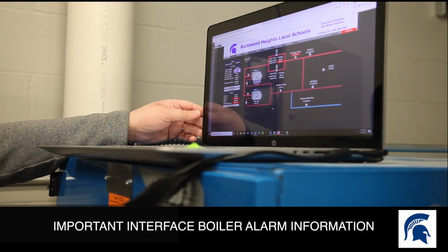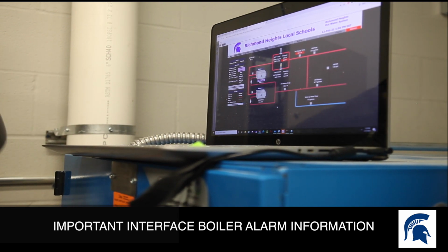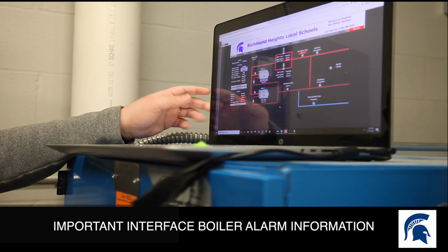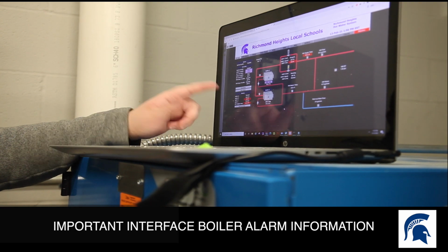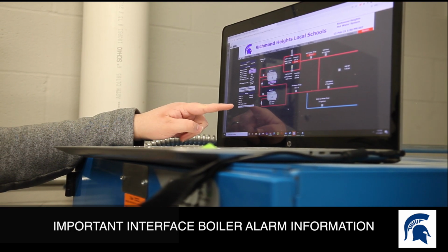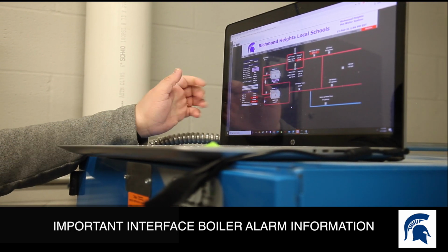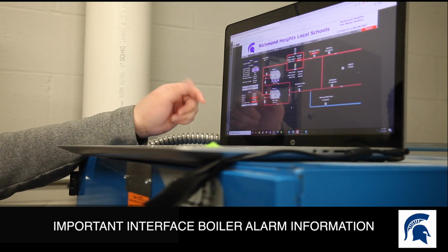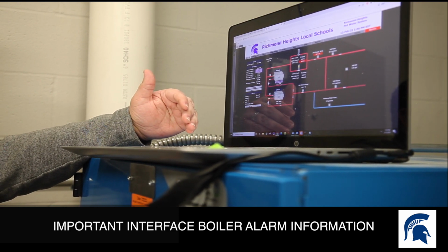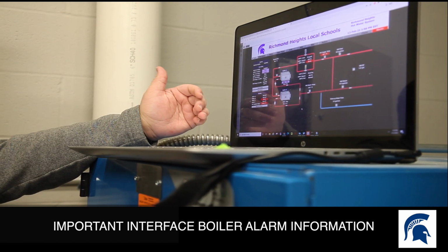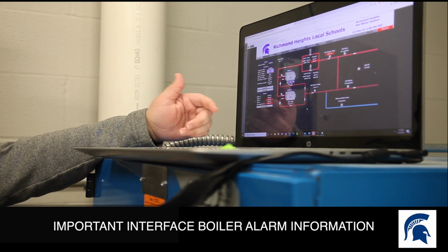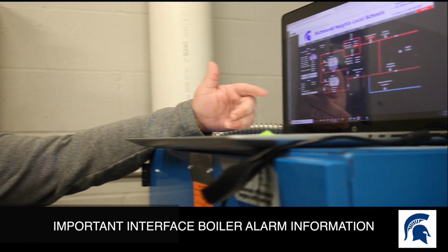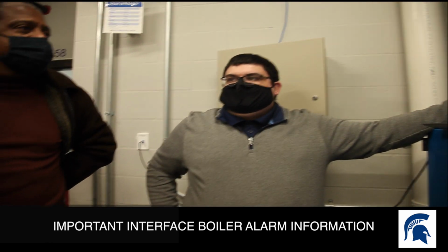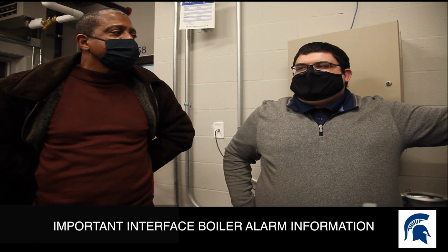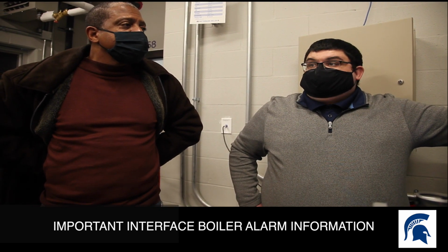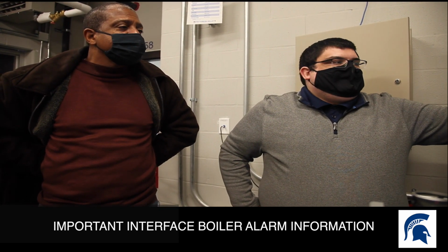So there's some alarms going off now? Yeah, because they're working on the pumps. So you see hot water pump 1's in alarm, and the hot water supply temperature is low. Those are both configured to actually send an alarm email out, so that if it's Saturday and your hot water gets down to 100 degrees, it'll send an alarm email and say your hot water temperature is too low, you want to go look at your building.